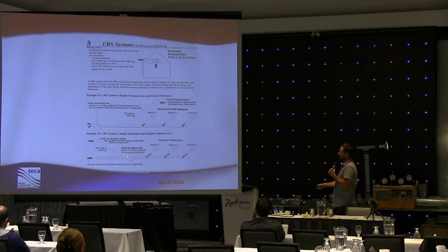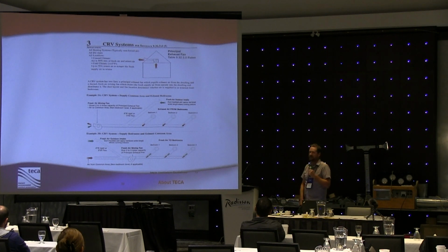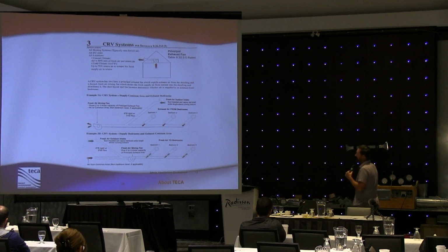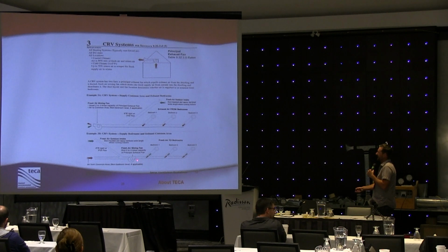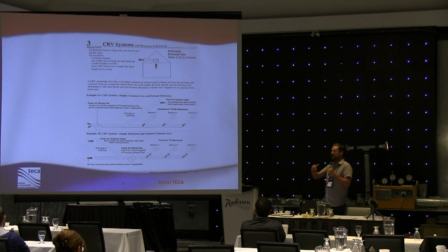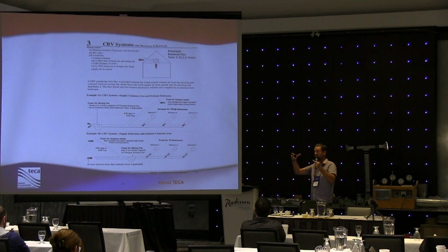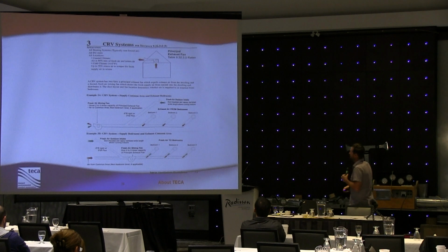This fresh air mixing fan is going to consume a bit more energy, namely because it's 2 times the size of this fan, but it's going to consume more than 2 times the electricity because it's ducted on both sides. There's going to be an impact to how much energy it takes to move that air. Typical bathroom exhaust fans are ducted on the exhaust side. However, typically they're an open grill in the bathroom, so there's no ductwork connected to them on the inlet side.